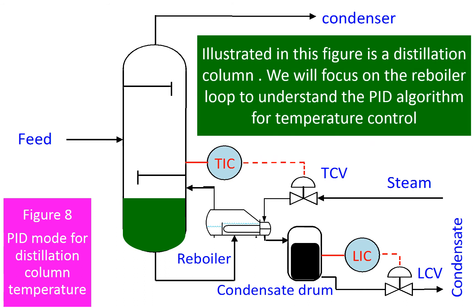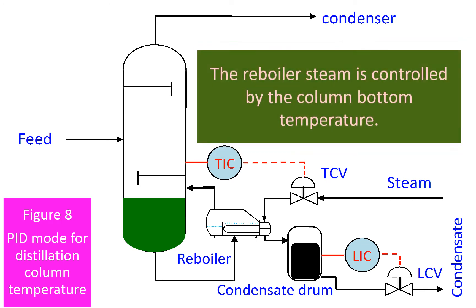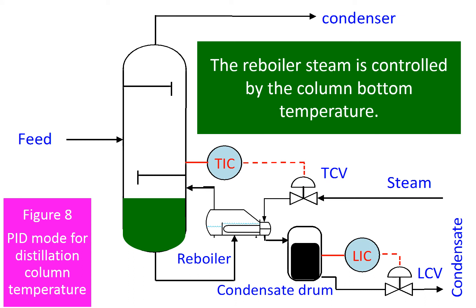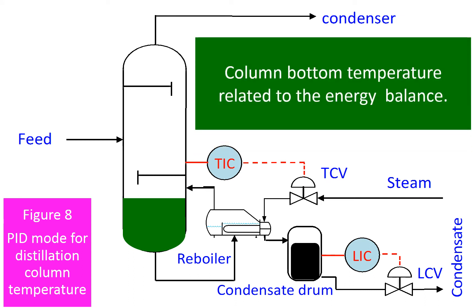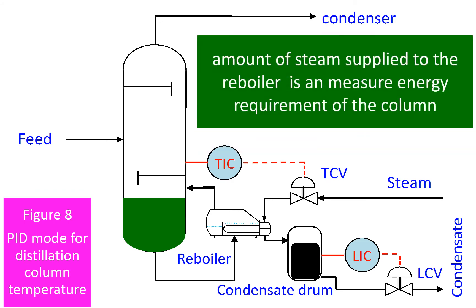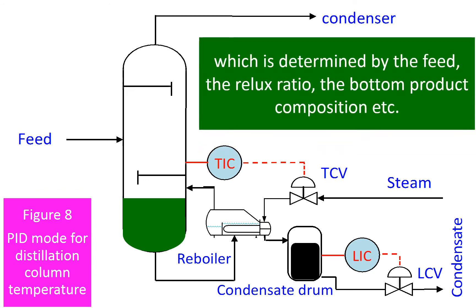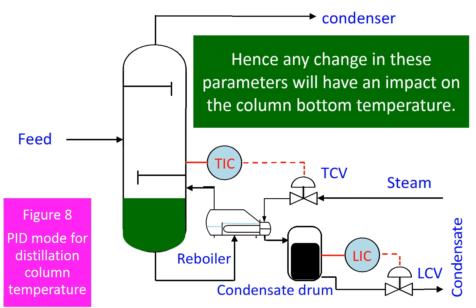The reboiler steam is controlled by the column bottom temperature. Column bottom temperature is related to the energy balance, and the amount of steam supplied to the reboiler is a measure of the energy requirement of the column, which is determined by the feed, the reflux ratio, the bottom product composition, etc. Hence, any change in these parameters will have an impact on the column bottom temperature, and it will take time for the system to respond.